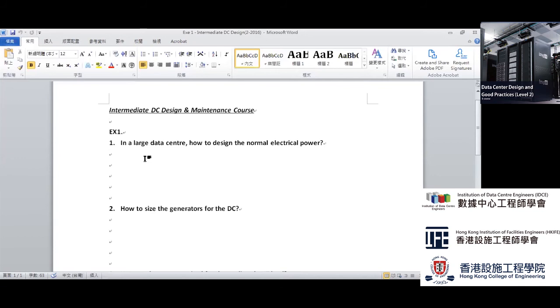don't forget, if it is a data center, you have to put in the actual racks power. For example, if you know the number of racks, each rack could be either 2 kilowatt or 4 kilowatt or 6 or 8 or 10 or 20 or 40 kilowatt per rack. Right, that's the normal power, of course. And then the air conditioning. Suppose you have a rack of, make it easy, 2 kilowatts.